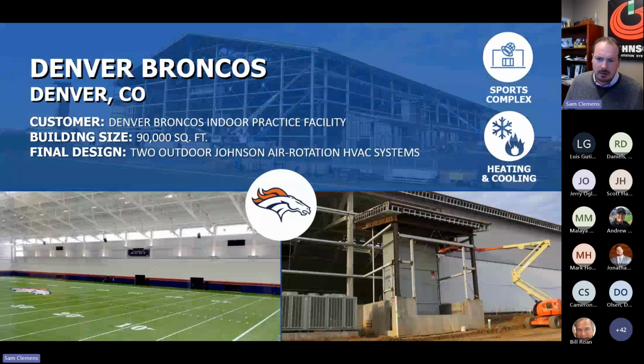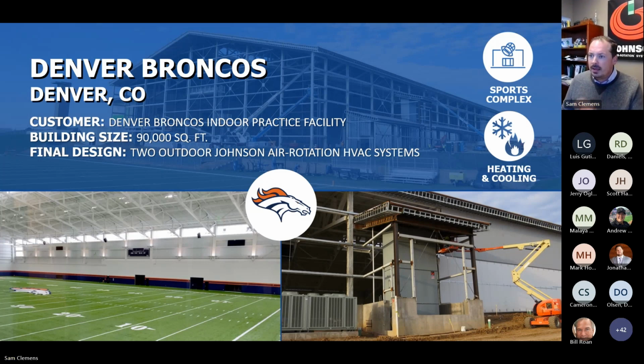But in the recreational world, there in Denver, the Broncos practice facility is actually conditioned by 2 Johnson air rotation units. These guys were preceded by the New York Giants. At some point, somebody looked at that and said, hey, these practice facilities look an awful lot like a big warehouse without racking inside of it. Wouldn't it be nice if we could get rid of the trunk lines you typically see down these facilities with slot diffusers and HVLS fans or distributed equipment? And lo and behold, it works beautifully well.